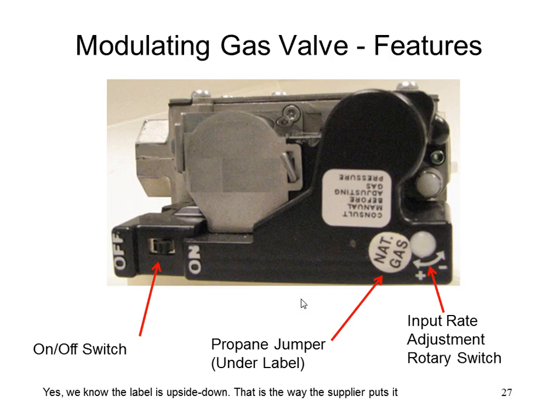That's a picture of the modulating gas valve. In and of itself, it's not all that exciting. It is a little bit different than some of the other modulating gas valves you might have used before on either other furnaces or on makeup air units and things like that. Most of those modulating gas valves that you can buy have a calibration ability to them that you adjust with a screw, kind of like we have on the right side of this picture. But with those ones, you calibrate them at the midpoint, and then you go test them at the lowest and highest fire to make sure everything's okay, which means that you kind of have to do it a couple times to kind of get the curve right.